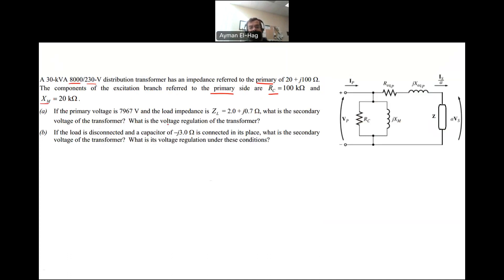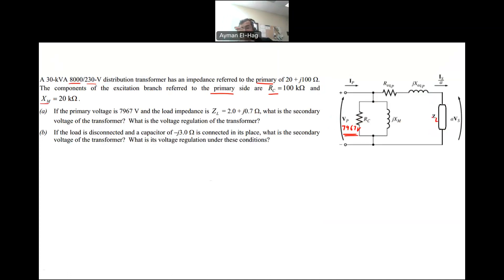If the primary voltage VP is equal to 7967 volts — so the voltage energizing the transformer is 7967 volts, which is a bit less than the rated 8,000 volts — and we have a load ZL connected to the secondary side equal to 2 plus j0.7, what is the secondary voltage VS?